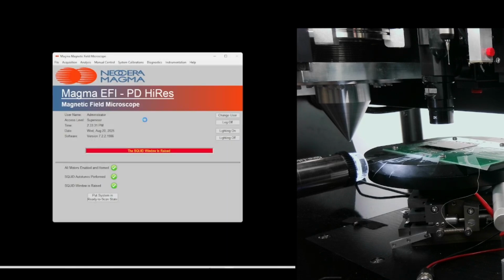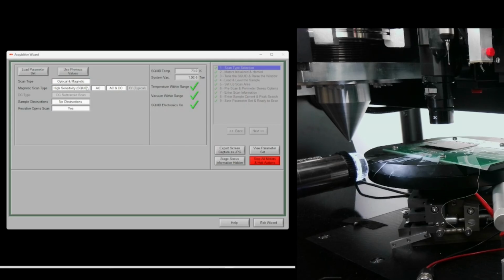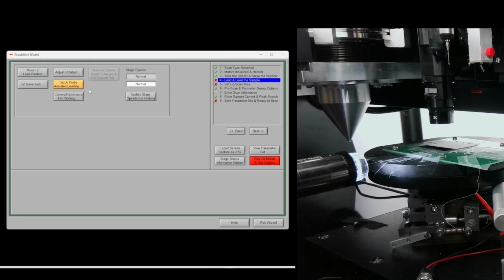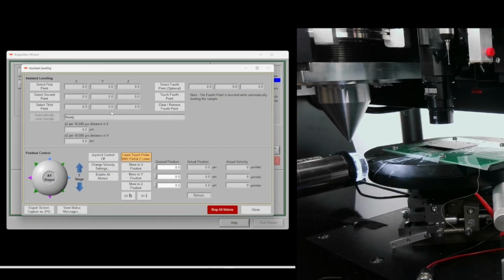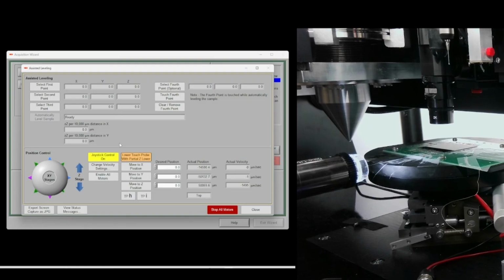After reviewing the scan parameters, we close the setup box and head into the acquisition wizard. Here, we start by changing the scan type to magnetic. On the far right, where it says XY typical, we switch that to line scan. Next, we begin preparing the leveling. We click on Touch Probe Assisted Leveling and then lower the probe using the partial Z lower option.